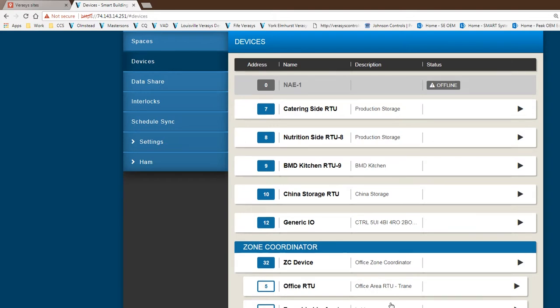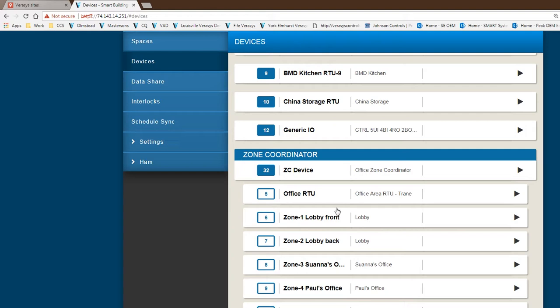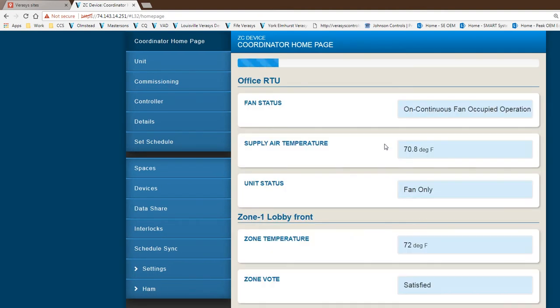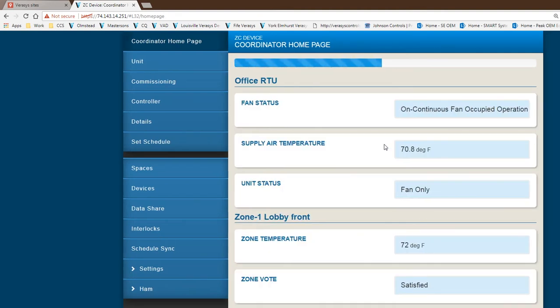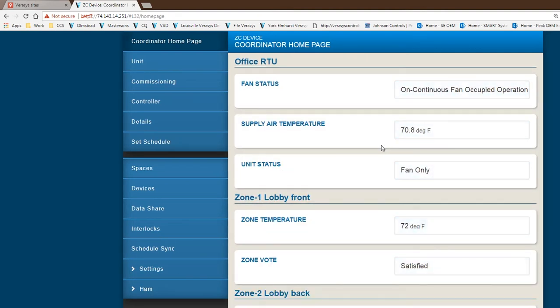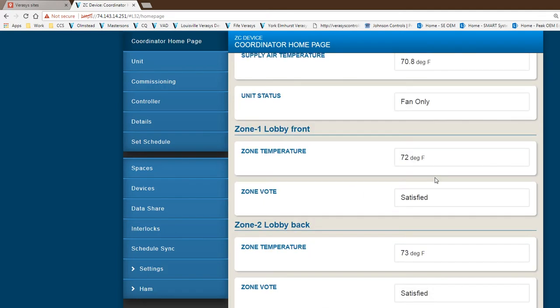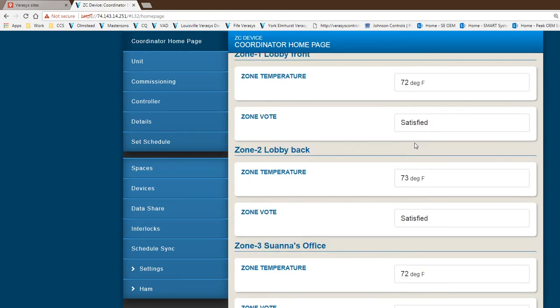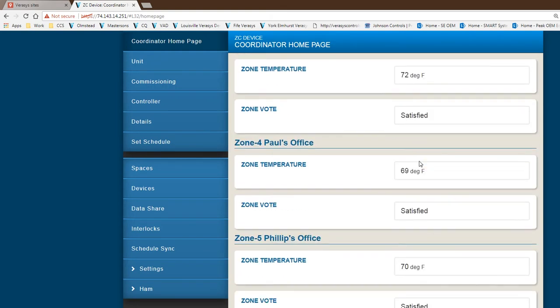The other piece from the device list is the zone coordinator. This is typical for a zoning system, both on a changeover bypass or a VAV system. At the highest level, when you click on the zone coordinator, you find the upper higher level of information of all the zones. It tells you what the rooftop is doing, is it on, is it continuous, gives you high level status. This is live information. It also gives you information of all the zones associated with that rooftop. Zone one in this case is satisfied with its zone temperature, and then the remaining zones.